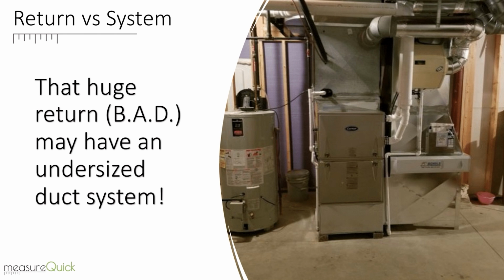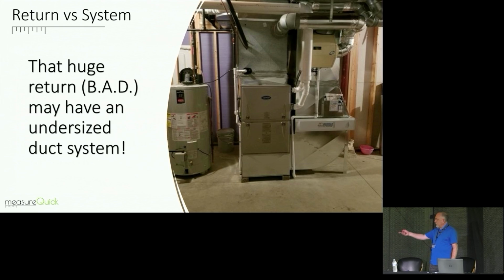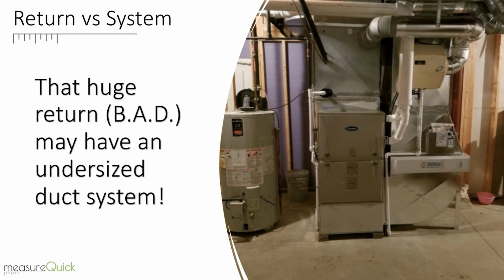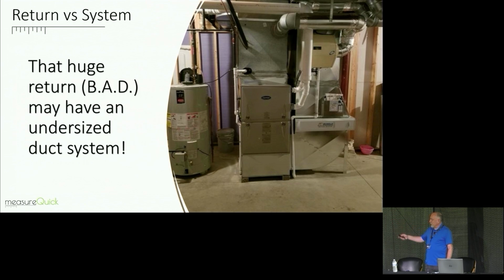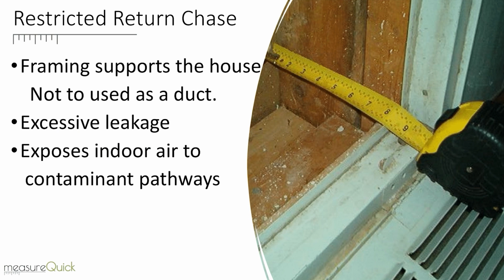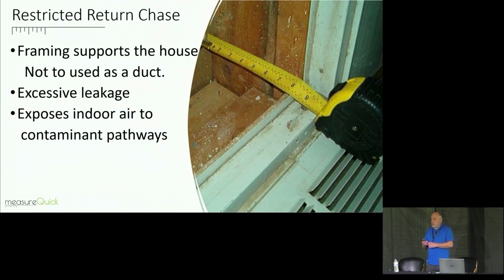Common problem. A lot of times, again, we're trying to fix everything at the equipment. Contractor puts in a huge, we call it the bad drop. Some people say big ass drop. And they're trying to get better filtering of the air. But if you start tracking that back, and this one went all the way back to a 2x4 joist space, it was reduced down to a 2x4 wall cavity for the return. Huge drop, huge amount of static pressure on the return. And again, if we're not paying attention to that, we're going to miss it.